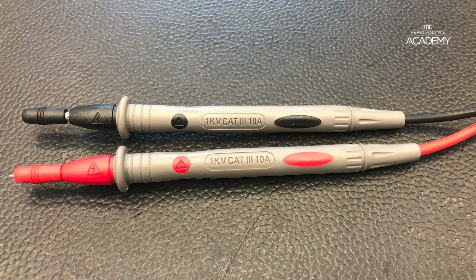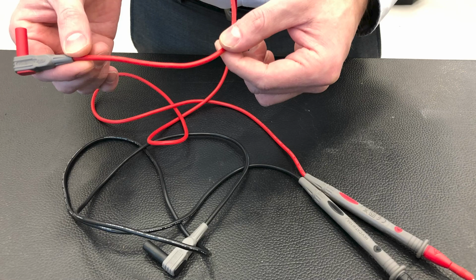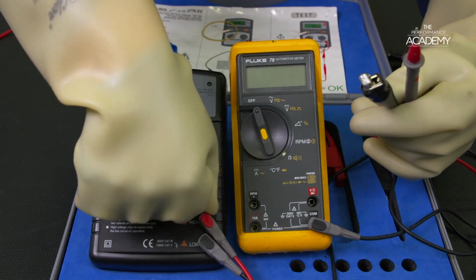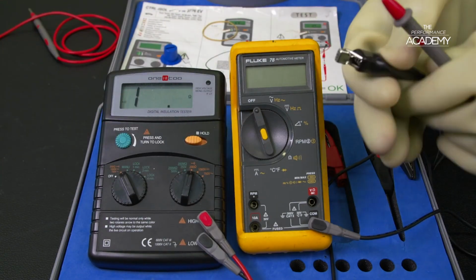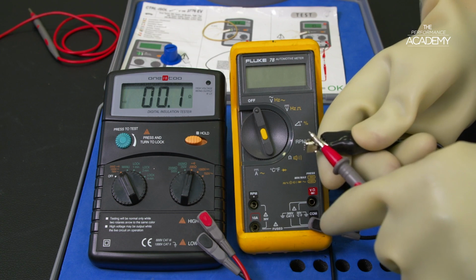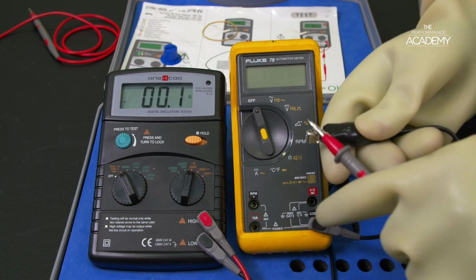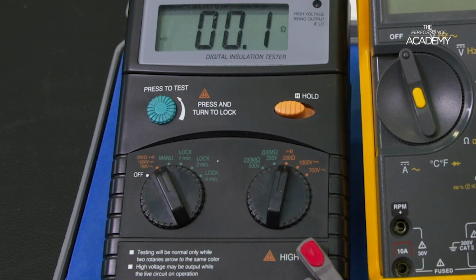First, we carry out the 3 checks on the test leads themselves. First, check to ensure they have Cat 3 600 volt or higher insulation rating. Second, we check them for any damage to the insulation connections or terminals. And third and final check is a continuity and resistance test. We need a very low internal resistance of no more than 0.6 of an ohm really. This is easily done by using the normal resistance test settings, coloured orange, on the insulation tester.